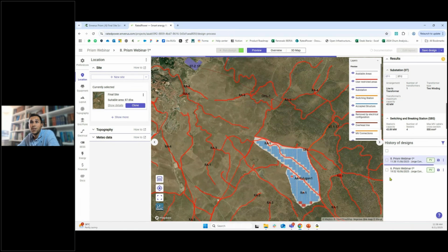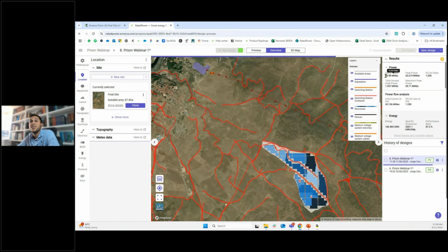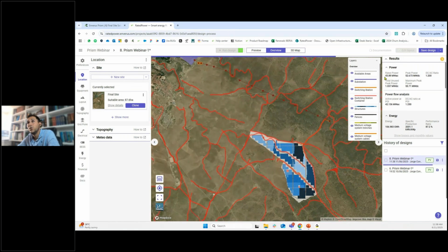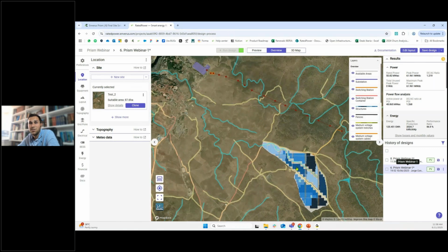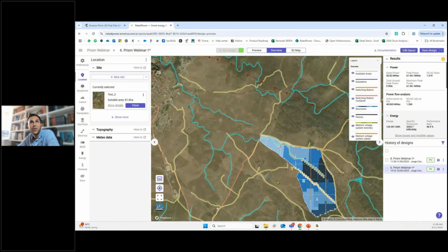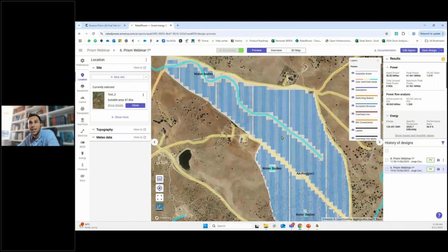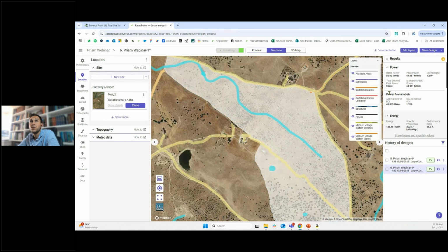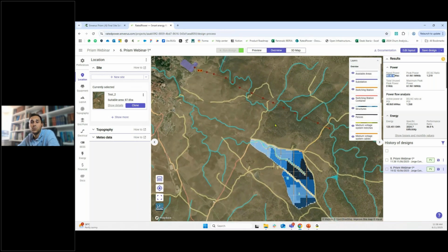Cool. That's exactly what I did. You see that, and you can tell that it's outputting 43 megawatts AC. I pretty much did an adjustment on the 6th design, and you will tell that with some adjustments, giving different namings to the different restricted areas, different colorings, different configuration for the structures, alignments, etc., then we could achieve to have those 50 megawatts that we were aiming to have and to connect to that substation.